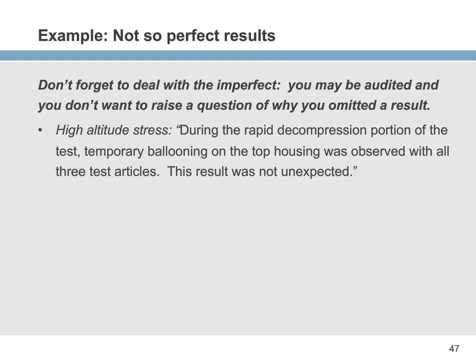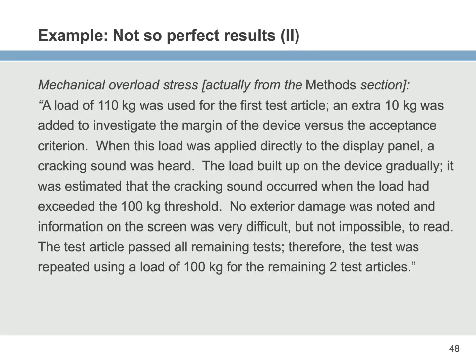Here's one a little harder. Mechanical overload stress: the acceptance criteria was 100 kilograms - basically crush the thing up to 100 kilograms in a bunch of different directions. A load of 110 kilograms was used for the test article, with an extra 10 kilograms added to investigate the margin of the device versus the acceptance criteria. That's pretty typical - you want to know not just did it meet the acceptance criteria, but how much margin do you have?